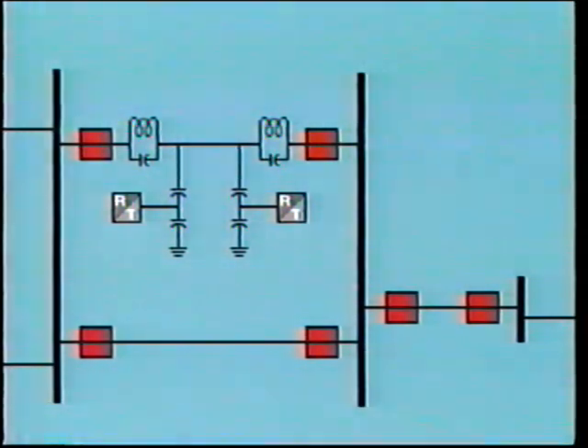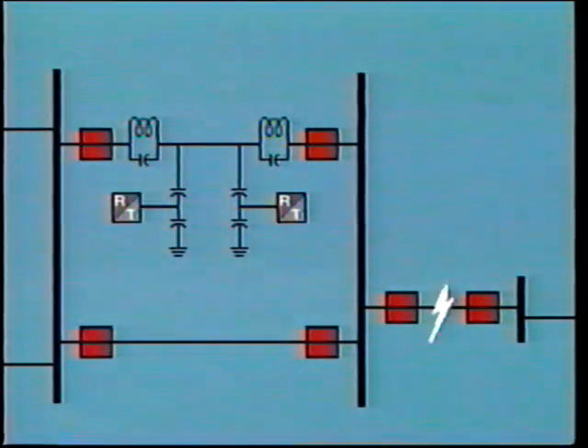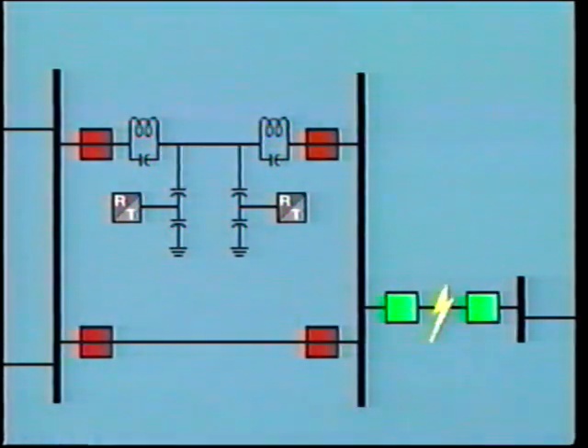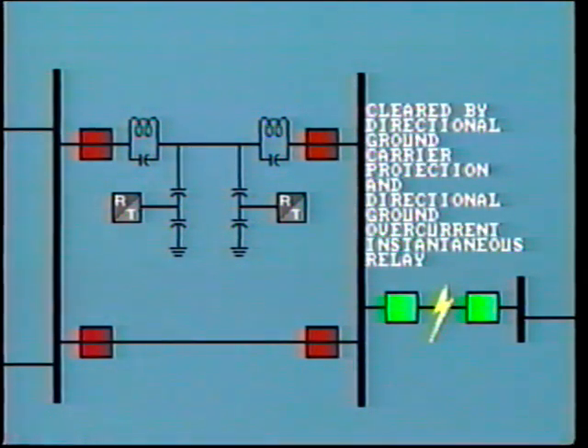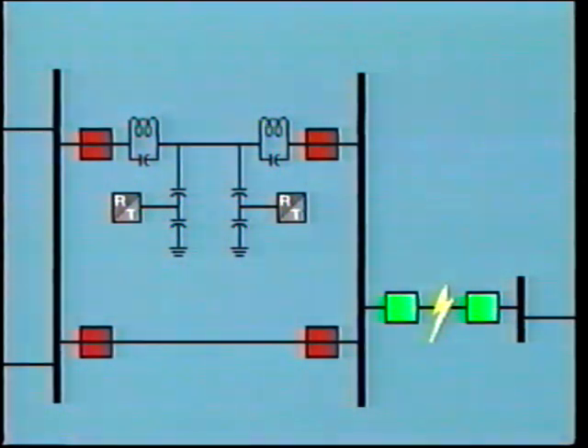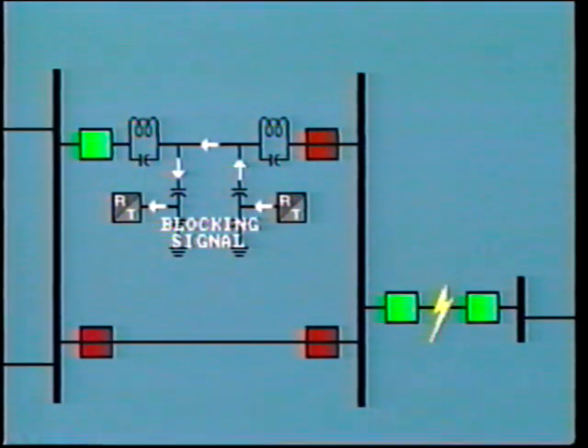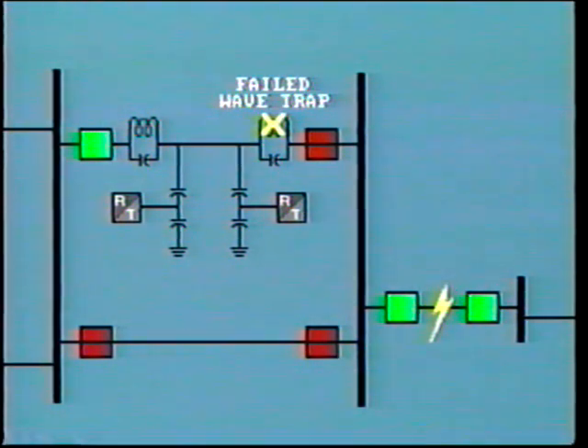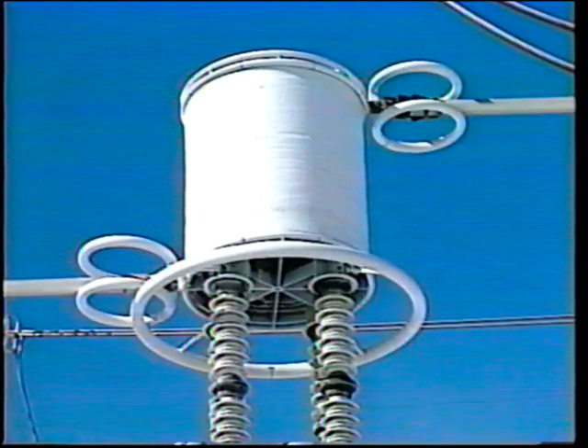Let's look at another example. In this system, a ground fault developed on this line due to a failed lightning arrestor. The line cleared correctly by operation of the directional ground carrier protection scheme and also the directional ground overcurrent instantaneous relay. But look, out here we also have a breaker trip, and this is incorrect for an external fault. Investigation showed that this breaker failed to receive the blocking signal over the carrier system. The problem was due to a failed wave trap, so that the signal was lost. This wave trap was replaced and the system put back into service. Once again, this faulty wave trap and associated carrier system may have remained inoperative for some period of time until discovered at the next routine test.